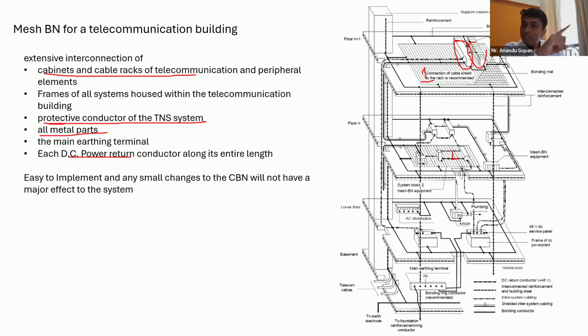And the major requirement is this mesh must have 1 milliohm resistance between two adjacent points. That is the major requirement in this mesh. There is no mesh sizing required, but you should achieve that 1 milliohm requirement between two adjacent points. So as long as you achieve this, the mesh sizing can be anything. It can be 1 meter by 1 meter, 2 meter by 2 meter, 5 meter by 5 meter. Or if you cannot achieve it, you will have to use a stricter, much more strict mesh.